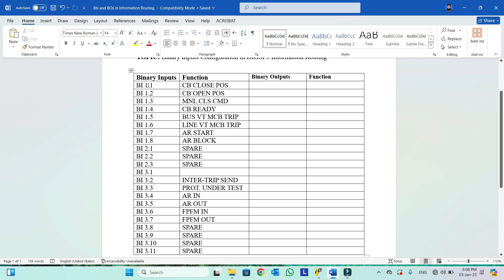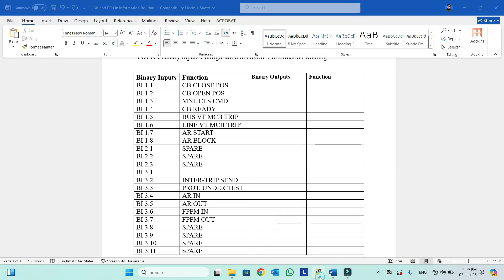For example, binary input 1.1 is CB closed position — this is the function and this is the binary input number column. So binary input 1.1 we need to assign against CB closed position. We will go in DIGSI 5 and see how we can assign this CB closed position to binary input 1.1.